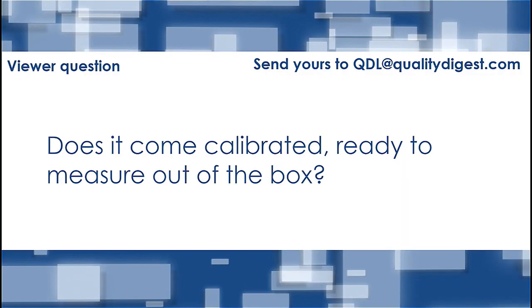Let's see. I'll take this one. Does it come calibrated, ready to measure right out of the box? Right, like we got into before, you're going to want to calibrate your probe and your laser. The new probes that come with the Quantum, you calibrate them once, and then they're ready to measure. Calibration takes a few minutes. It's a very simple process. It comes with the calibration cone. Everything you need is included with the system. Those NIST traceable certifications are available once a year, as long as you maintain your warranty. But it's pretty much a plug and play system.